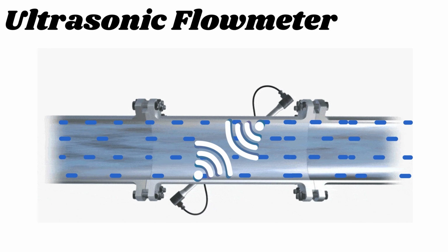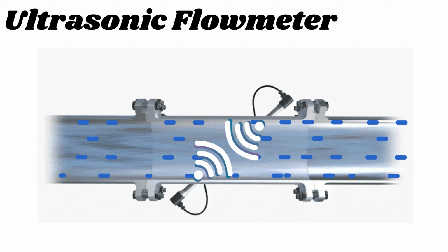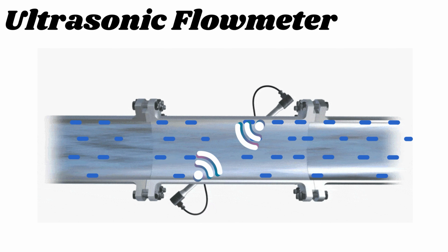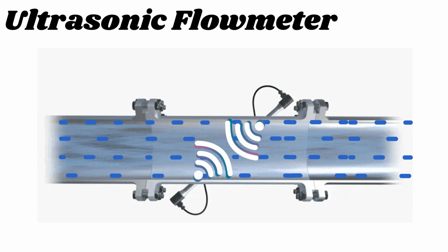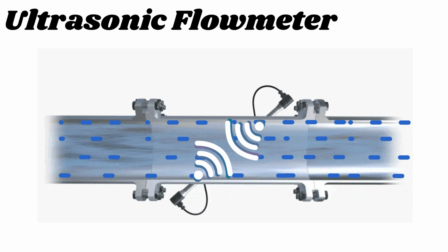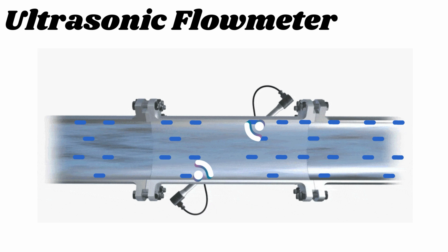Ultrasonic flow meters. The ultrasonic transit-time principle consists of two opposing probes, the first placed upstream and the second downstream. Each probe of a chord alternately transmits and receives an ultrasonic wave directed towards the other probe. The two travel times and the difference between the two times make it possible to determine the average flow velocity along the chord, and from this to deduce the volume flow rate.